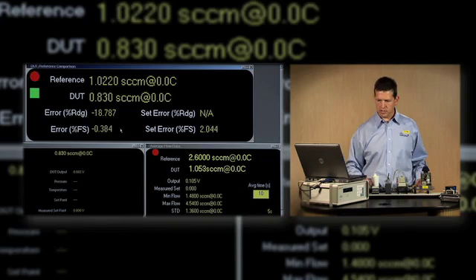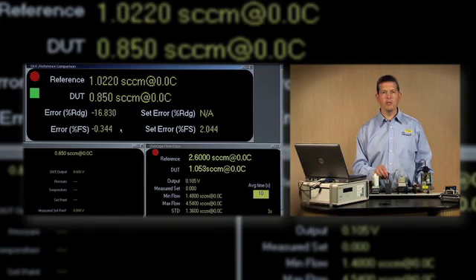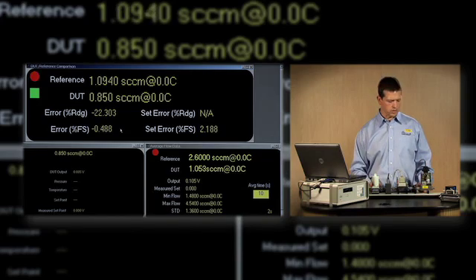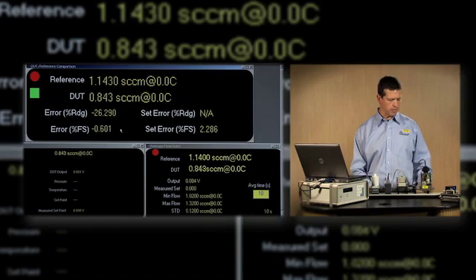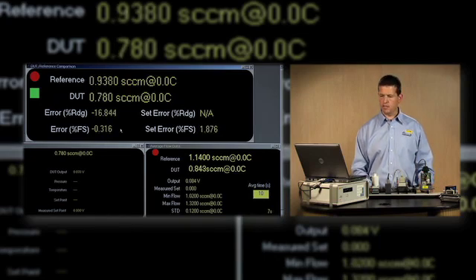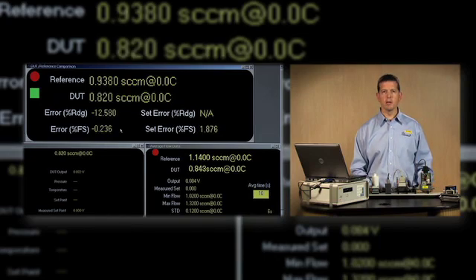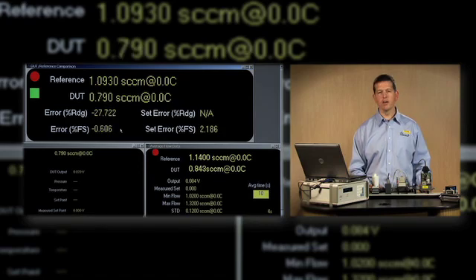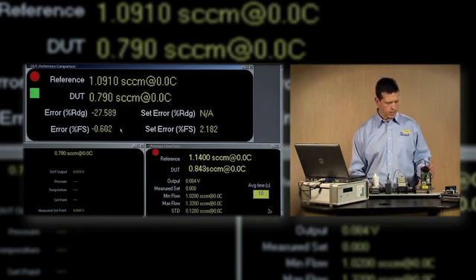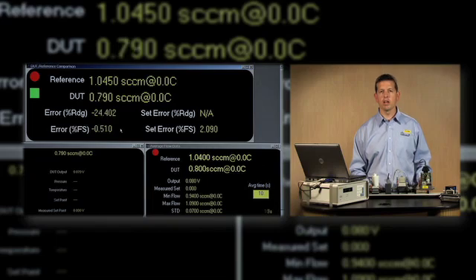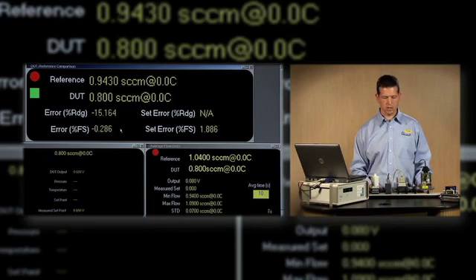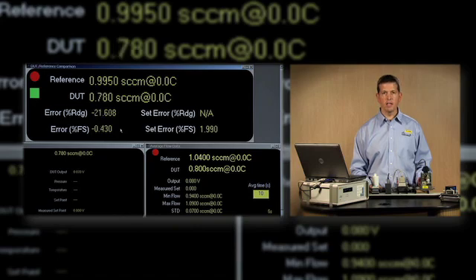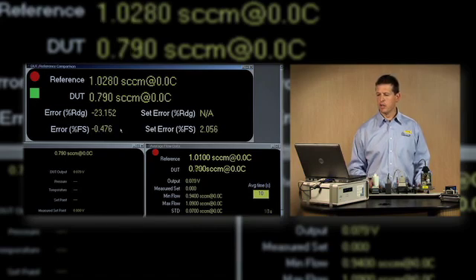Depending on procedures you have, you may need to or want to close the isolation valve and remove pressure from the MFC or even cap off the end of the MFC. I think since we're using measurement error rather than set error, I can just as well take the reading just like I did during the automated test, which is to allow the MFC's valve to close off the flow as best it can and compare the measurements between the molebox and the MFC as they are.